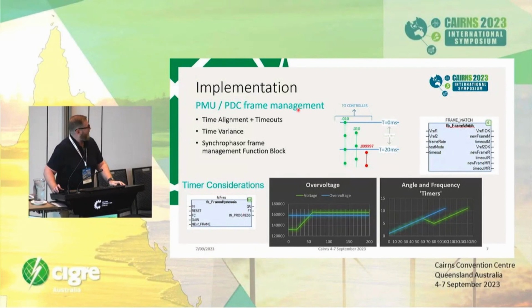So this is the nuts and bolts part of it. The logic is reasonably straightforward, but when it came to actually looking at how the synchrophasors would affect the system and how we need to process them, one of the fundamentals is that when you're streaming synchrophasors, time is critical, so you want to make sure you're using samples from the same time period to do any kind of comparison. For example, at 10 milliseconds, the arrival of all these synchrophasors is going to be asynchronous. So there needs to be a point where you say, okay, something hasn't arrived, you need to move on with life.